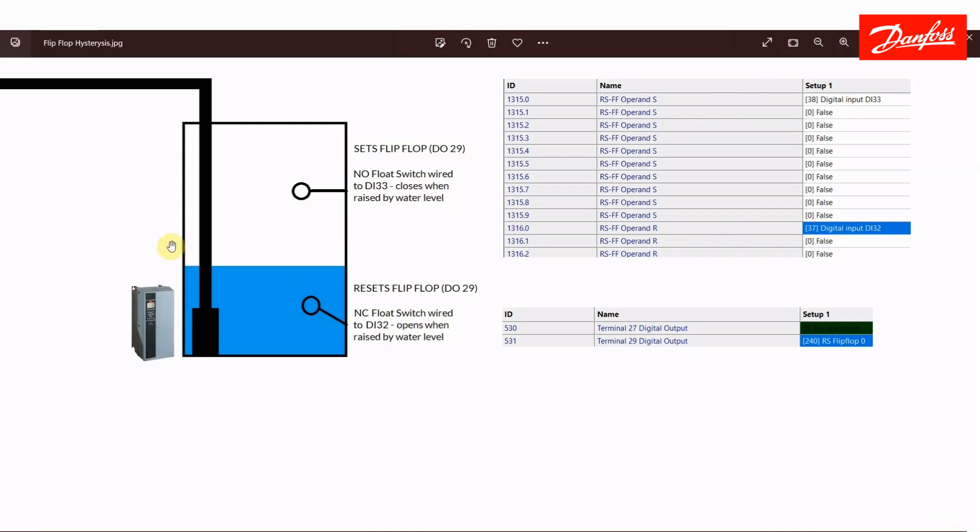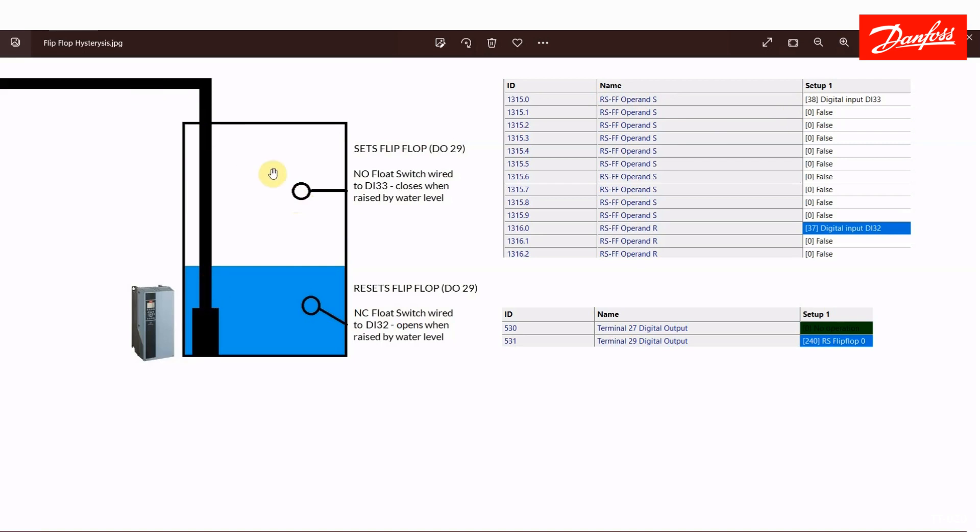Okay, so here's the flip flop I set up. I'm looking at two switches. Digital input 33 will set the flip flop and digital input 32 will reset it. Again, I have a digital output attached to this flip flop. So to set the flip flop, for this example I'm trying to do a tank level control here. So when the water levels at this high level and this normally open switch lifts and closes, that's going to set the flip flop. So that's why I have the RS flip flop operand for digital input 33.